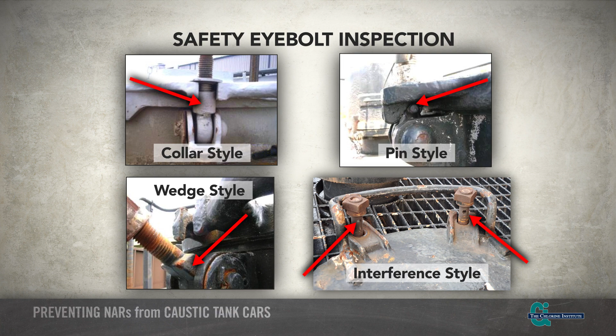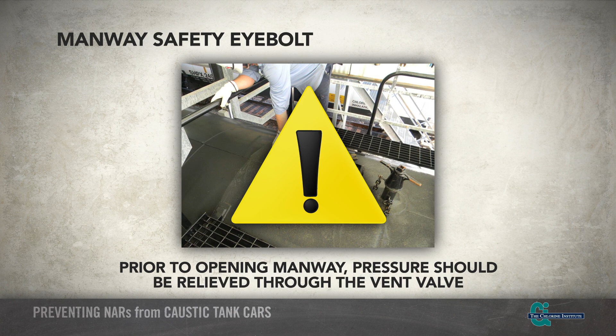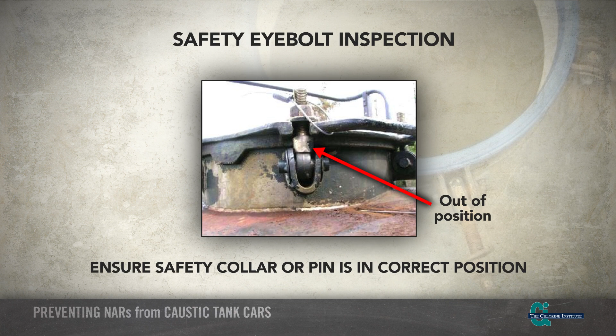As shown here, there is a collar, pin, wedge, or interference-style safety eye bolt, until the cover is opened up to about 3/8 inch. They prevent the eye bolt from rotating downward, thereby allowing the tank to relieve pressure before opening the cover all the way. During inspection, it is important to ensure that the safety eye bolt is in the correct position and is not damaged to prevent securement.